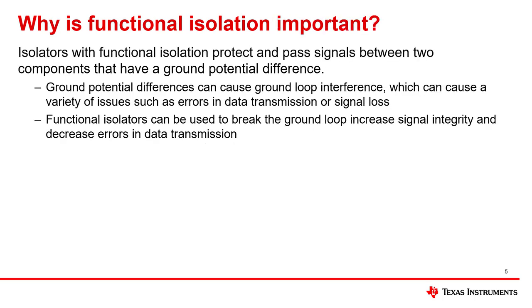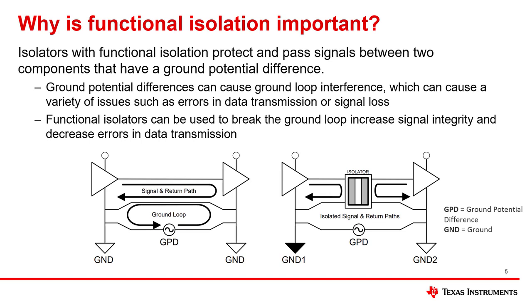Functional isolators protect signals against high ground potential differences. Ground potential difference is the voltage between two different circuits. These voltage differences cause ground loop interference, which can cause errors or signal loss in the data being transferred between two circuits or systems. Functional isolators mitigate this issue by breaking the ground loop and separating the two circuits or systems, allowing for an increase in signal integrity and reduction in data transmission related issues.